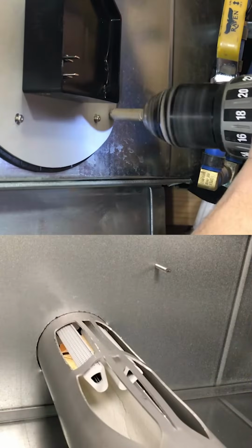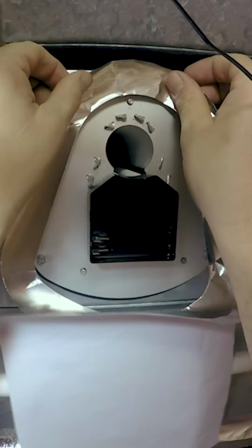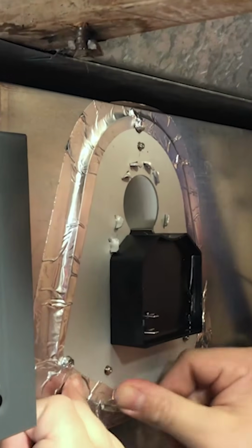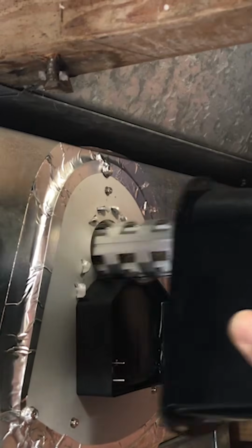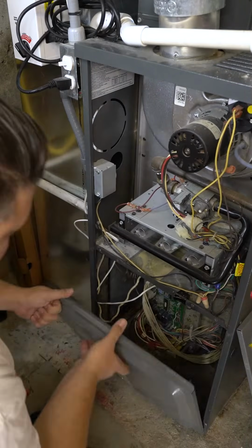After pressing it together, secure the unit with the provided screws through the holes on the mounting plate. Next, apply the aluminum sealing ring or comparable foil tape that complies with local codes. Press firmly around the entire surface to ensure an airtight seal. Finally, insert the outer plastic housing into the opening and twist to lock it in place. Now we can move on to the electrical connections.